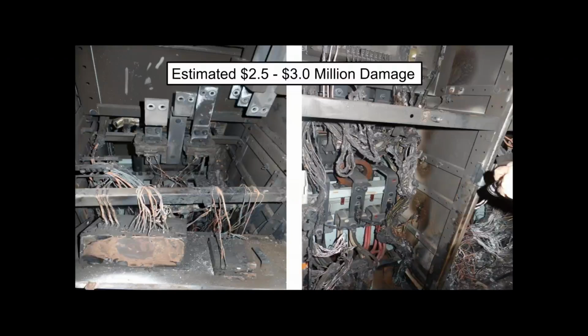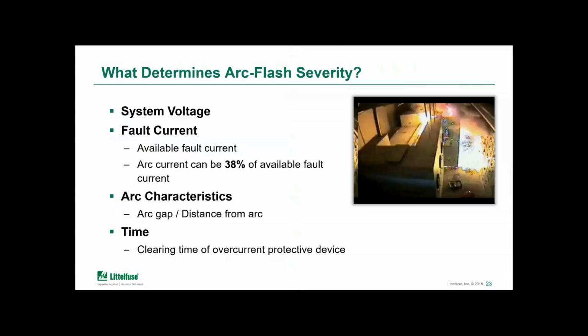I'm sure that many of you have seen all kinds of photos of equipment that's been damaged by arc flash, but aside from the safety risks, of course, there are the risks to the equipment, which create uptime and operations issues for the plant, and a liability as well. The costs really can skyrocket if you have to leave the entire plant offline until a particular critical piece of equipment can be rebuilt or replaced. And as I'm sure you're aware, for a lot of that critical equipment, the lead times can be measured in weeks, not days. So that can have a pretty big impact on plant operation.